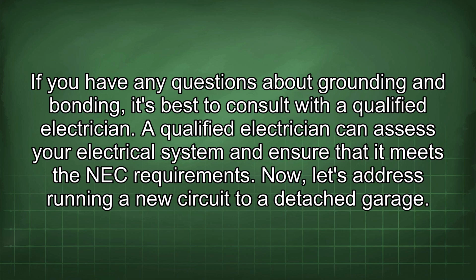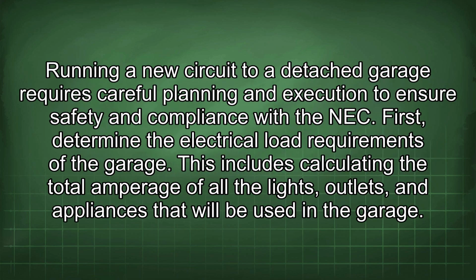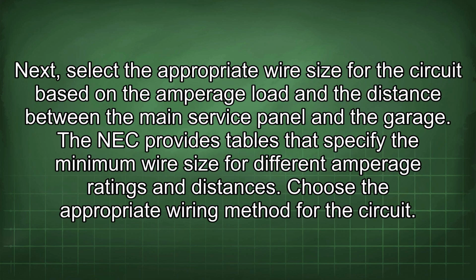Now let's address running a new circuit to a detached garage. Running a new circuit to a detached garage requires careful planning and execution to ensure safety and compliance with the NEC. First, determine the electrical load requirements of the garage. This includes calculating the total amperage of all the lights, outlets, and appliances that will be used in the garage. Next, select the appropriate wire size for the circuit based on the amperage load and the distance between the main service panel and the garage. The NEC provides tables that specify the minimum wire size for different amperage ratings and distances.